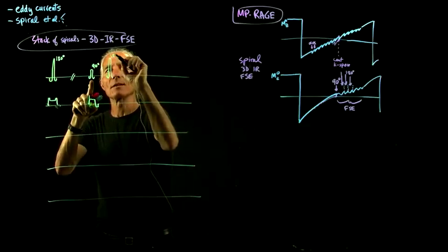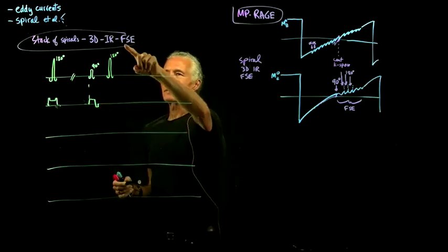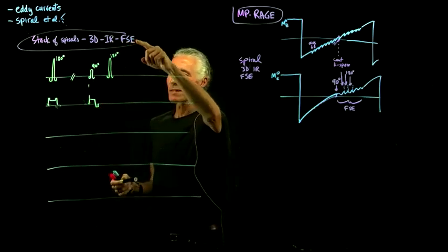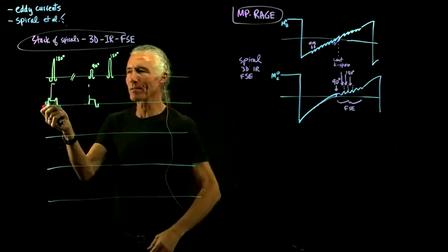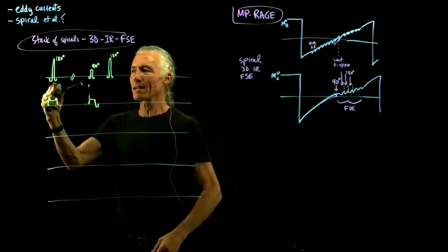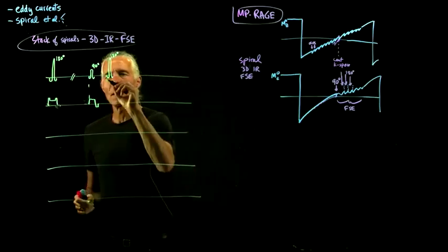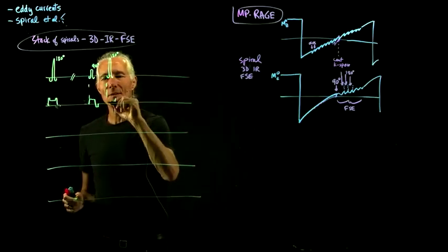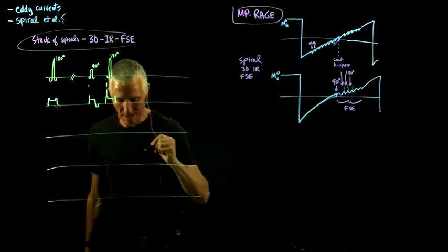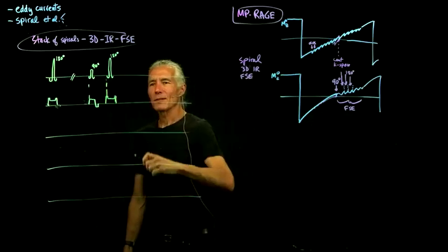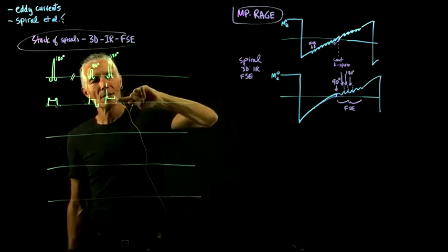So now here's our spin echo. So it's inversion recovery spin echo. So there's two different kinds of 180s. The one that sort of does the inversion to get the contrast, and then the 180s that make the echo train. And so now we have a bunch of 180s here, and so we have to slab select those guys. But it's a 3D scan, and so what do we do now?